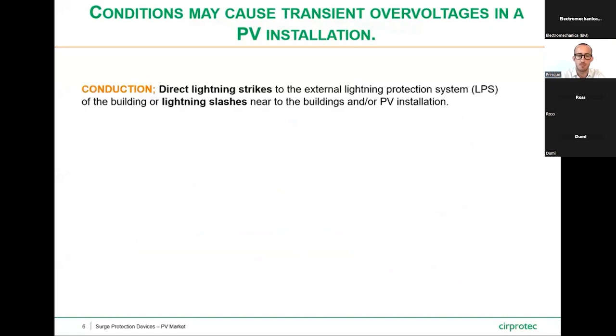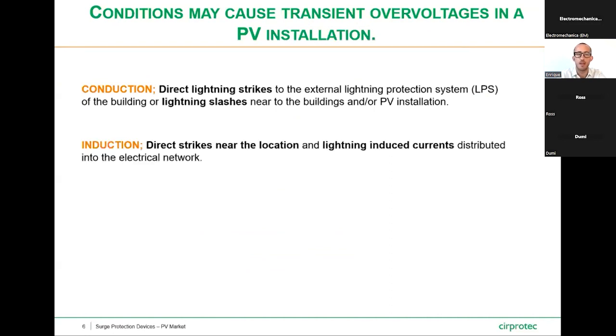Which are the conditions that may cause transient overvoltages in a PV installation? The first one is the one named conduction. Conduction means direct lightning striking the external lightning protection system, which is the lightning rod of the building, or lightning strikes near the buildings and/or the PV installation. Then we have another condition named induction, which means lightning striking near the location and inducing currents distributed into the electrical network.